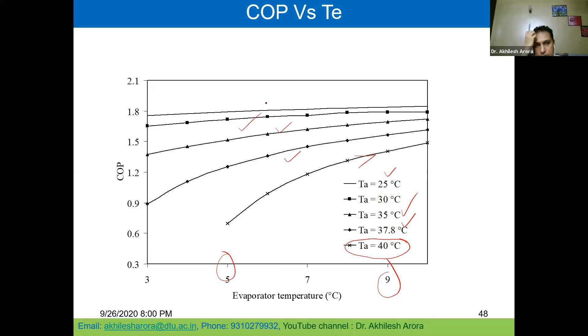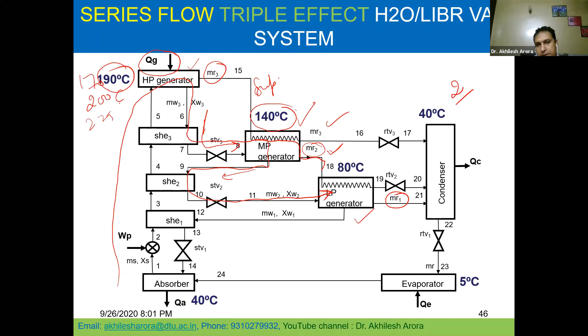Now this is the parallel flow triple effect system. Though it's 8, I will take 5-10 minutes more and finish it off. As I told you, I have prepared according to the time, so hardly 10-15 minutes I will take. Once again, like the previous system, it is a series flow, because the strong solution goes to the HP generator first, passes to the solution heat exchanger, goes to the MP generator, then passes here, from here the solution goes here, then goes here. It is flowing in series, so it is a series flow.